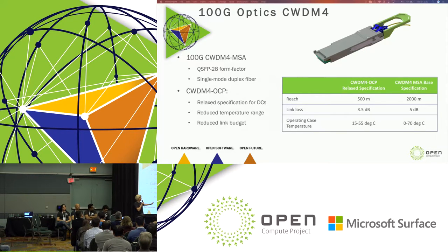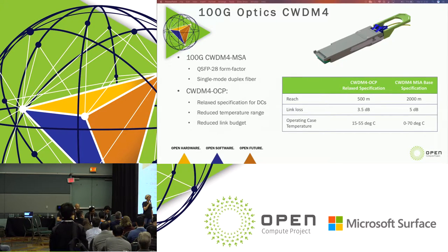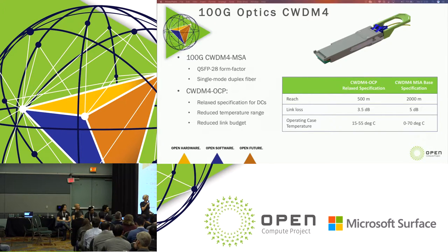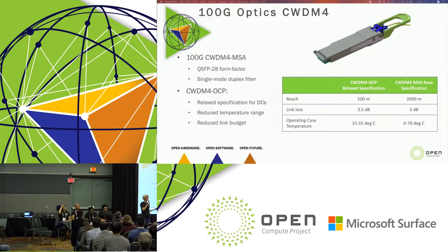We tailored the specification for our own particular environment inside a data center, which is a little different from what other end users use. For example, the telecommunications industry has stringent requirements on reach, temperature, and lifetime. So we tailored those specifications for a data center environment. The reach — instead of two kilometers from the MSA — inside our data center the longest length we could possibly need was 500 meters. We've defined the link loss appropriate for that distance and the number of connectors. The operating case temperature is also reduced: instead of zero to 70°C, we control it to 15 to 55°C — about half the temperature range.